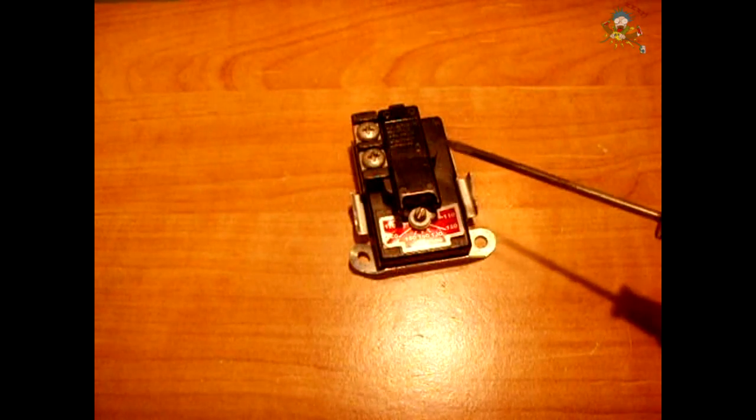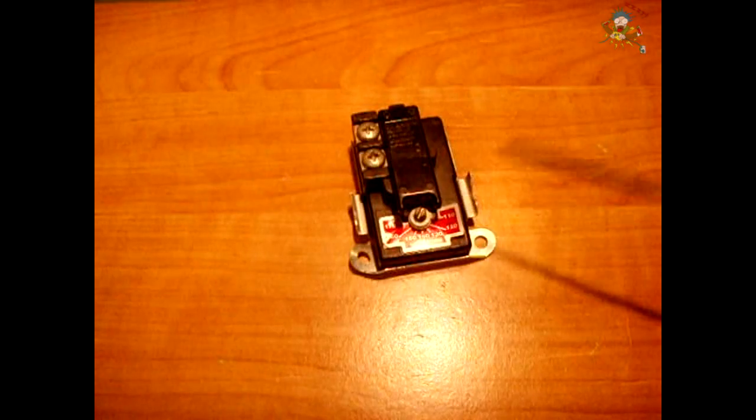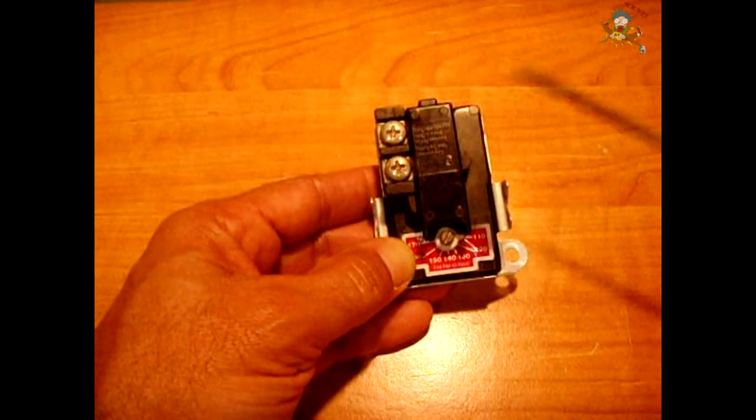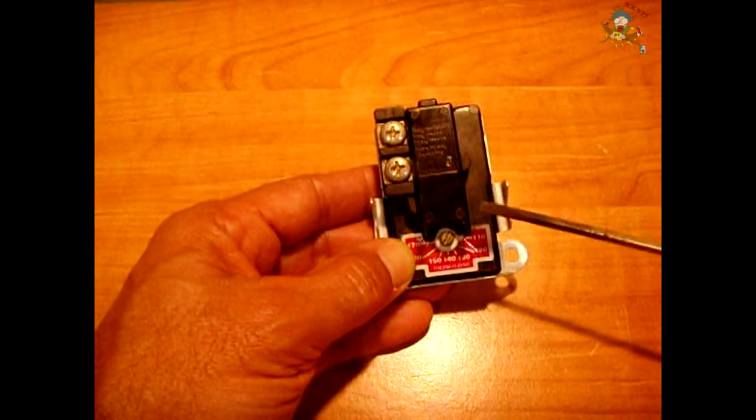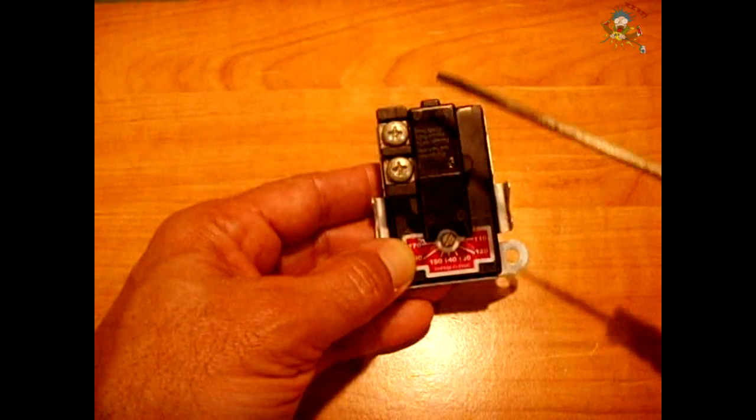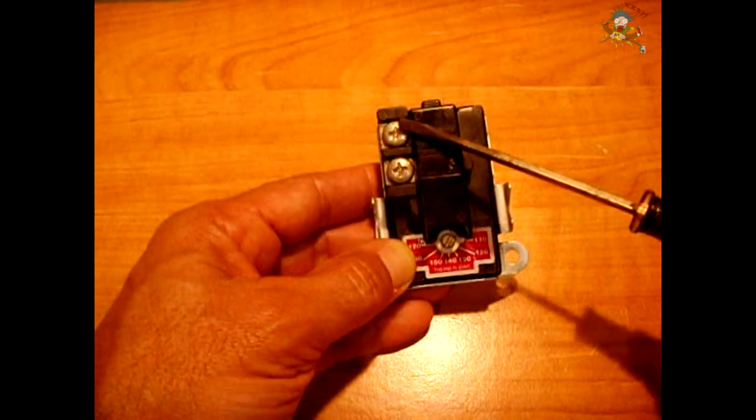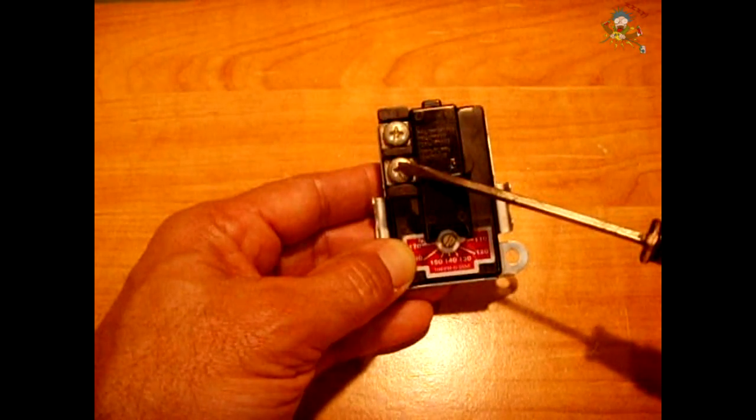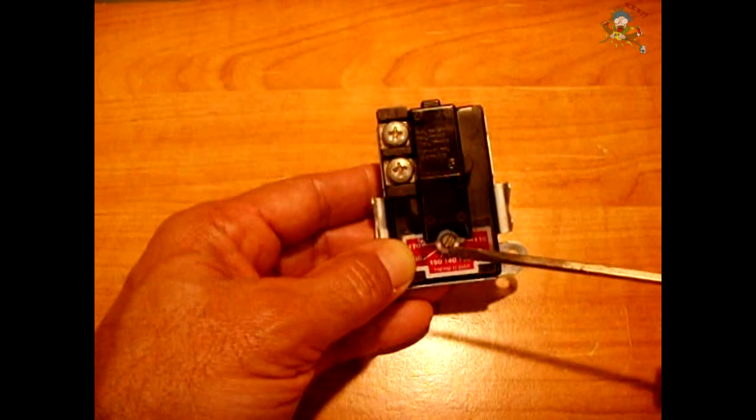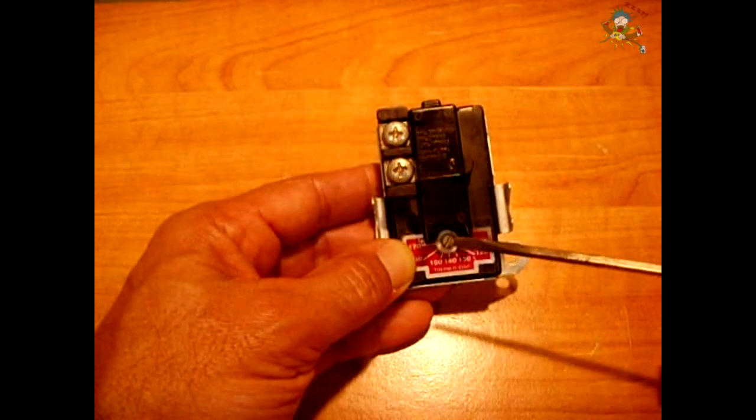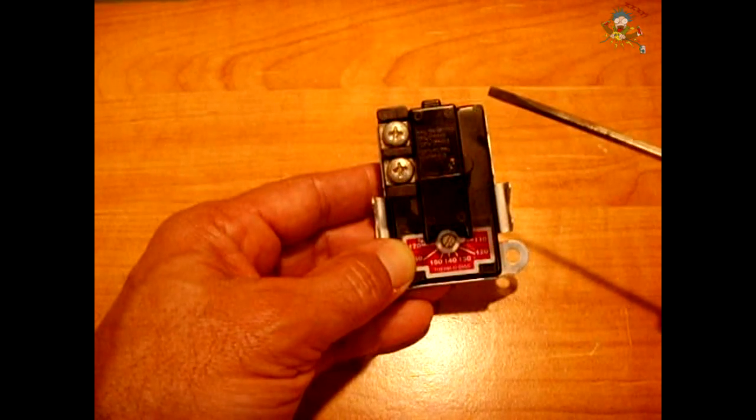Now as you can see here, this thermostat is a lower thermostat. There's only two connections. The power wire would flow into one screw, and then from the other screw would go into the heating element. And then the other screw on the heating element would complete the circuit with the other 120 volt leg.